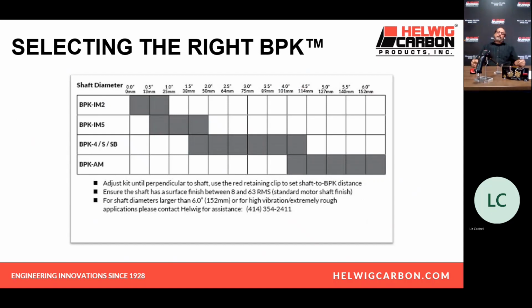Another big advantage that Helwig offers, if you have motor shafts that are from 1.5 to 4.5 inches, which covers almost everything, you only need one kit. You don't have to have a different kit for each slight increase in shaft diameter. One kit does the whole thing. With our multi-fit bracket assembly, same bracket, same kit, same everything. Stock one kit, maybe two if you really have a wide variety of motors, and you have all of your motors protected. You don't have to purchase and stock a variety of mitigation solutions for every different shaft diameter. Don't have to drill and tap, don't have to put on some colloidal silver, don't have to use conductive epoxy, none of these things. Loosen the motor bolt, slide our kit on, tighten that same motor bolt right back down, walk away. Okay, it's pretty slick installation.